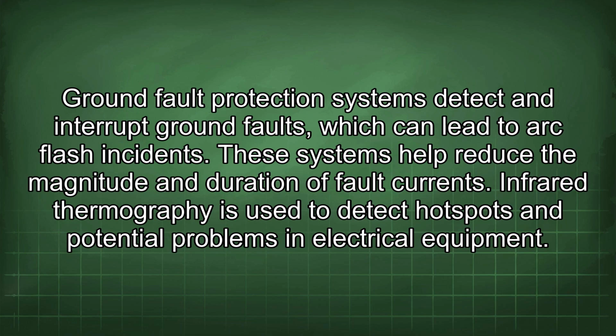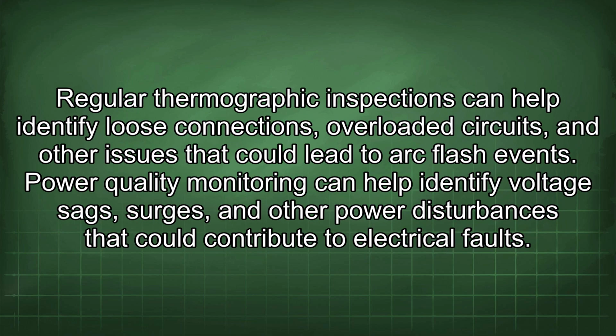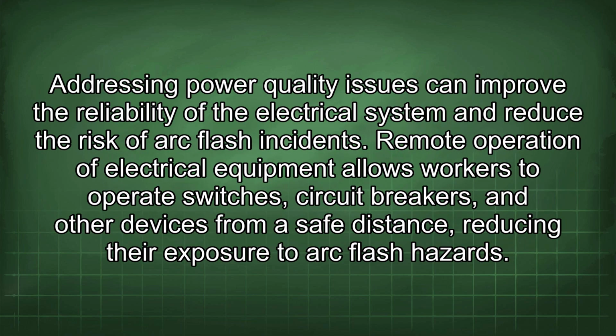Infrared thermography is used to detect hotspots and potential problems in electrical equipment. Regular thermographic inspections can help identify loose connections, overloaded circuits, and other issues that could lead to arc flash events. Power quality monitoring can help identify voltage sags, surges, and other power disturbances that could contribute to electrical faults. Addressing power quality issues can improve the reliability of the electrical system and reduce the risk of arc flash incidents.